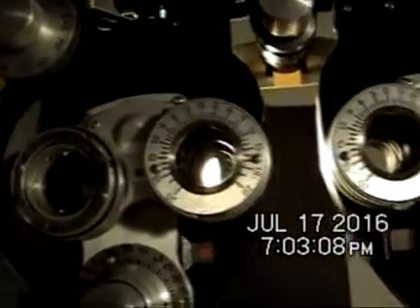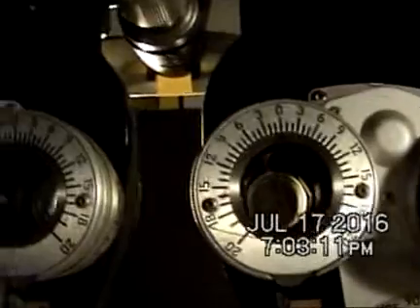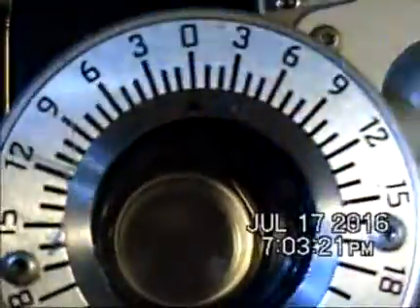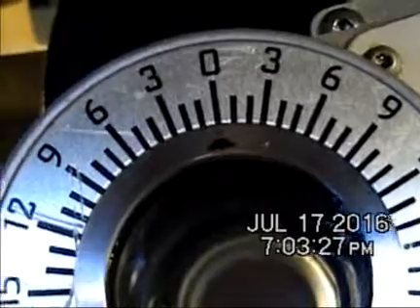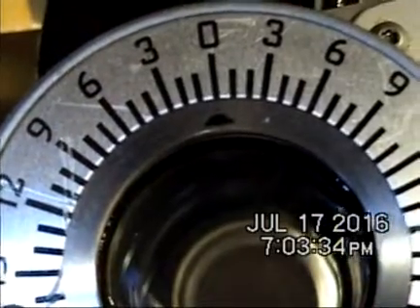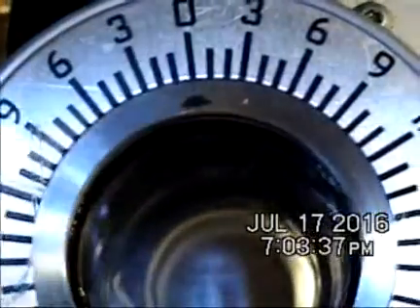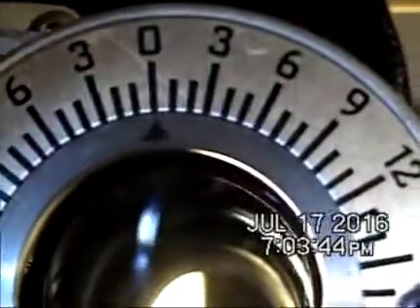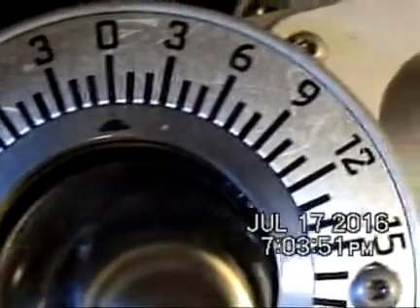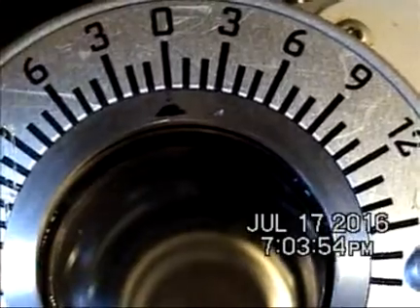This phoropter is more than 25 years old and I noticed that the marking on the Risley prism is starting to fade so that it's no longer as visible. This one is quite sufficient still — you can still see the point of the arrow — whereas this one has the distal third faded off.